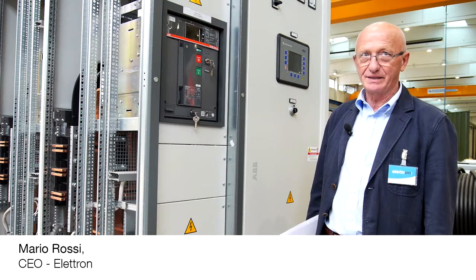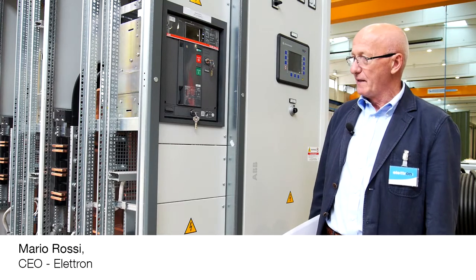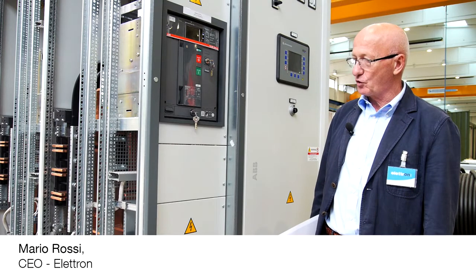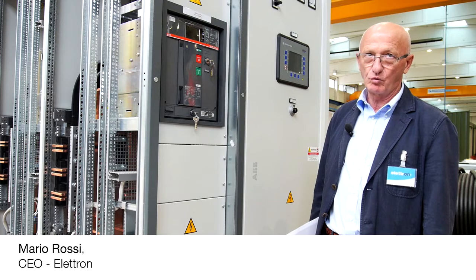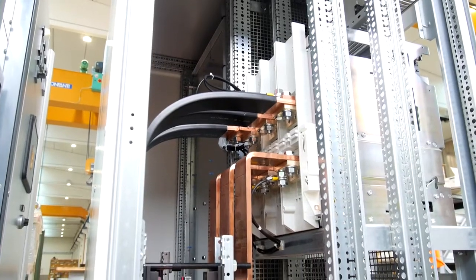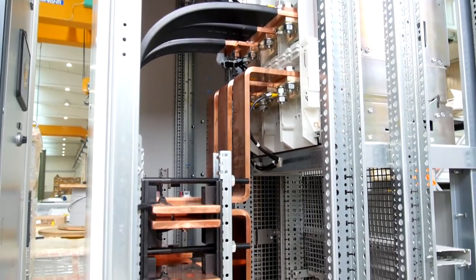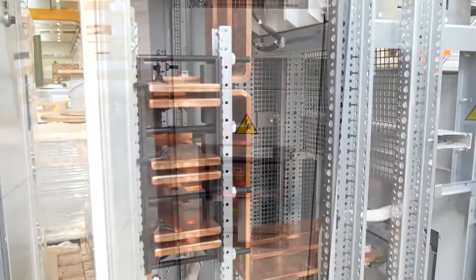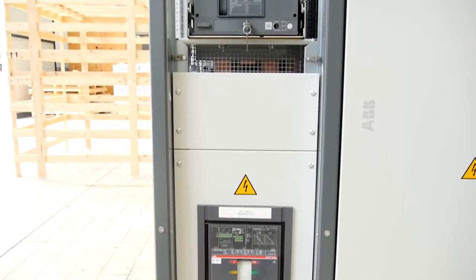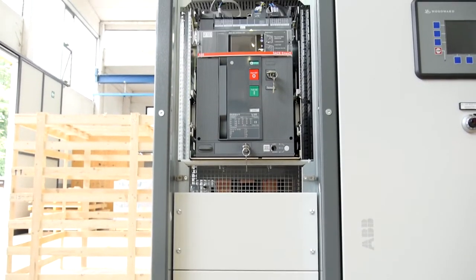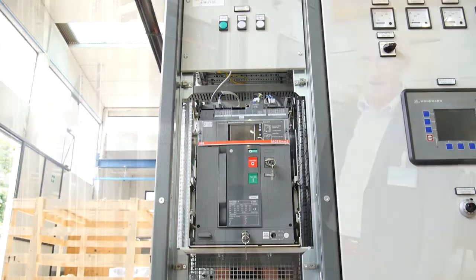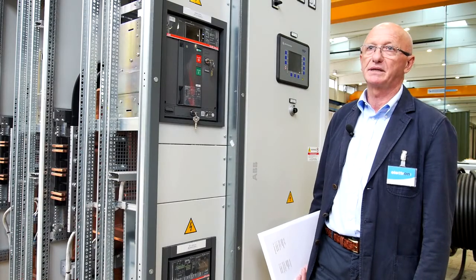It's worth highlighting the real opportunity that the Emax2 circuit breaker gives us: units of up to 2,500 amps can be applied within a width of 400 millimeters. Here we can see the positioning, one on top of the other, of two types of circuit breakers. And we even have the possibility, again within the 400 millimeter width limit, to make the breaker withdrawable.